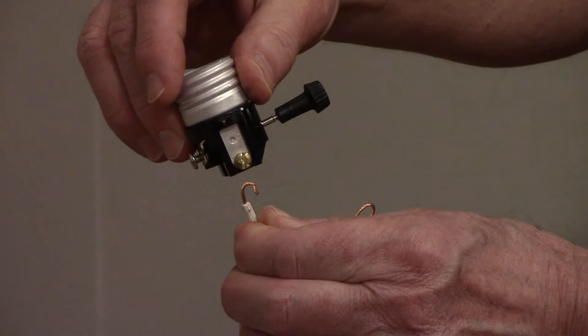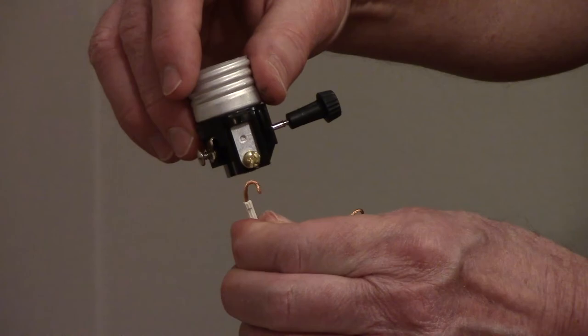With your loop, wrap it around the screw terminal in a clockwise direction. If you wrap it counterclockwise, it could potentially push off from the screw.